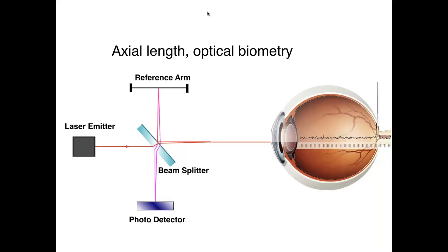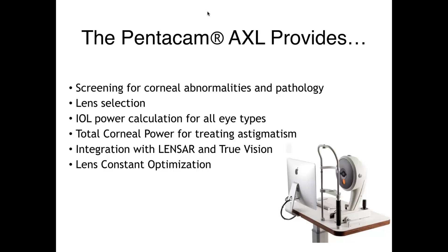With the Pentacam AXL, not only is this a high-resolution tomographer, but it also has a partial coherence laser interferometer added to the device that allows for high-resolution optical biometry. In our center, we've conducted pilot trials and validations against the IOL Master 500 and found excellent correlation in axial length. This integrates keratometry and axial length in a high-resolution fashion, screens for corneal abnormalities, aids in lens selection, allows for IOL power calculations for all eye types, generates total corneal power for astigmatism treatment utilizing both anterior and posterior corneal surfaces, and integrates with additional technologies through streaming such as LENSAR and TrueVision.